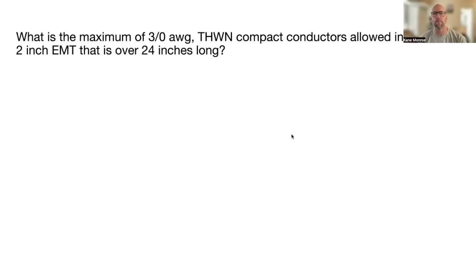What is the maximum of 3/0 awg THWN compact conductors allowed in a section of 2 inch EMT that is over 24 inches long? That's five of them. NEC Annex C, Table C1(A). Make sure you're looking in those compact conductor tables when you're looking this one up.